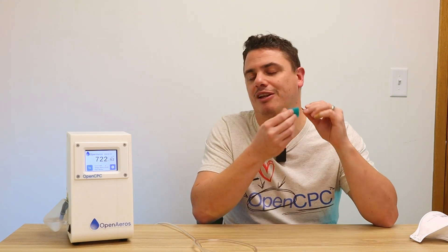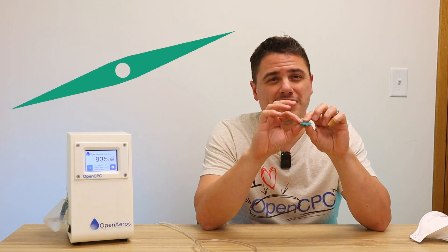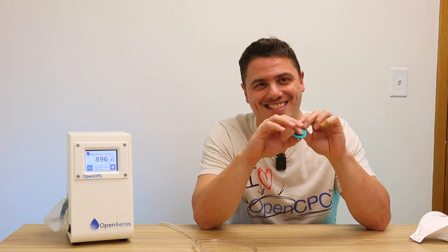Now I know what you're thinking: it's going to create a leak right where you slide that probe in. But it doesn't. The trick is making it very conformable — we use very soft silicone and a very nice continuous taper that goes all the way down to half of a human hair in thickness, and that ensures that you have a good seal against the skin.